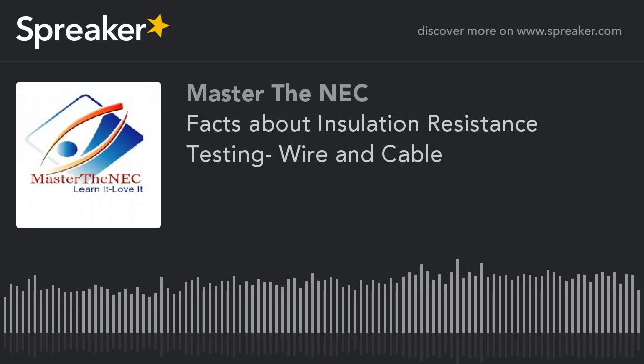Okay, that would be fine if their notion was that all of the insulation that I'm connecting to is potentially weak. And the notion that I'm sending out 500 volts DC into a conductor, and the conductor insulation is bad or has excessive amount of current leakage, that the other conductor that's next to it is going to be equally bad, and it's going to allow the absorption of that leakage current. That is kind of a misnomer. And if you don't believe me, pick up the phone and call the engineering departments for Fluke, Megger, or Hioki. I have. Now, they might tell you differently if they're trying to sell a product, but I have talked specifically, and I will put my reputation and name on the line to say I have talked to their engineers, and they have told me there is no reliable way that you can get a reading that's reliable between two insulated conductors.